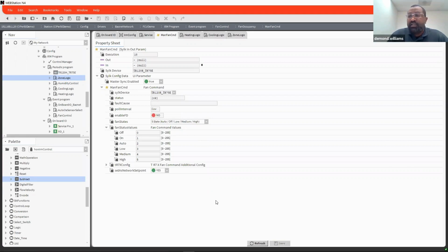So my logic behind it was, if the customer goes in, turns the fan off, and puts in a service call saying that the unit isn't working, and then the BMS group pulls it up, sees that it was manually turned off, they should be able to manually put it back into auto, and then the customer would be able to get the unit back on, or at least see what was going on. So if the automation group did something to the fan coil unit, it wouldn't necessarily lock the resident out from controlling their thermostat in their room.